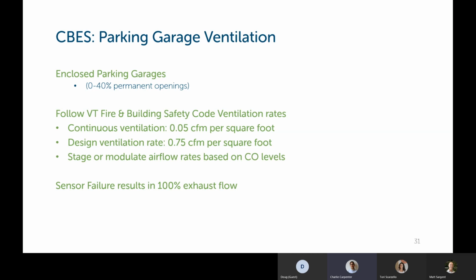you need to have a continuous ventilation rate of 0.05 CFM per square foot at all times, and the system must have the capacity to ramp up to 0.75 CFM per square foot of garage space, and that system must be staged between the continuous and design rate based on carbon monoxide sensors throughout the garage. Each sensor can only cover 7,500 square feet, and there's some other listings in there about how this system must stage or continuously modulate based on carbon monoxide levels in the garage. And if any of the sensors fail in the garage, the failure default is just to go to 100% exhaust in that area.